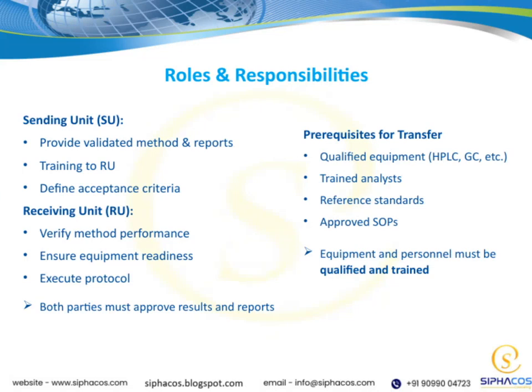Let's take a moment to discuss the prerequisites for a successful transfer. First and foremost, the equipment involved, such as HPLC, GC, and others, must be qualified. This means they've been validated and are functioning properly. Equally important are trained analysts who understand how to operate this equipment correctly.